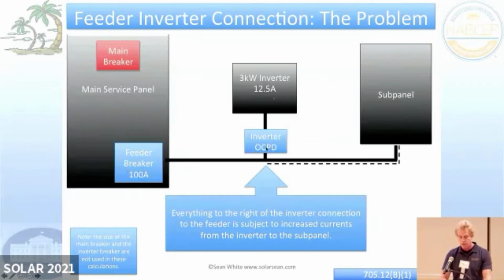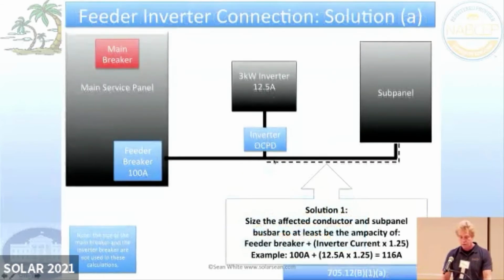So there are a couple of different solutions for how to deal with this. The first solution is if the conductor is big enough, you don't have to worry about it. You could swap out the conductor, or maybe it's already big enough before you ever showed up. And we don't use 12.5 amps in the calculation because when you're doing wire sizing, there are overcorrections and things like that. So we take 12.5 times 1.25, and that gives us 16. And so we just need to make sure that this conductor can carry 116 amps. That would be nice and easy. If that conductor can carry 116 amps, then we don't have to do anything.